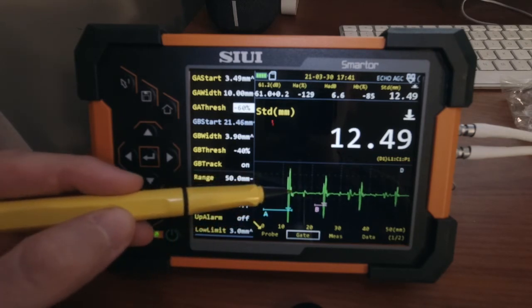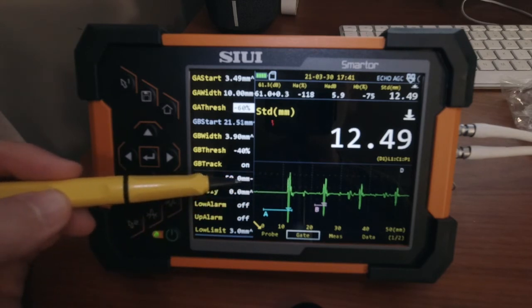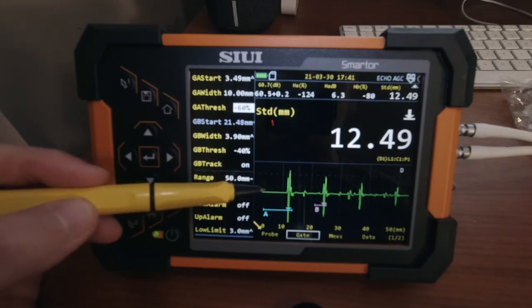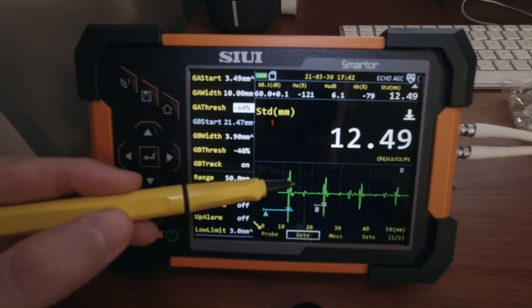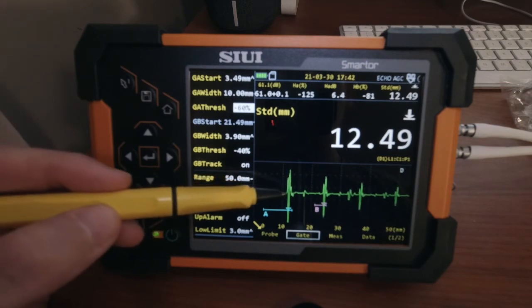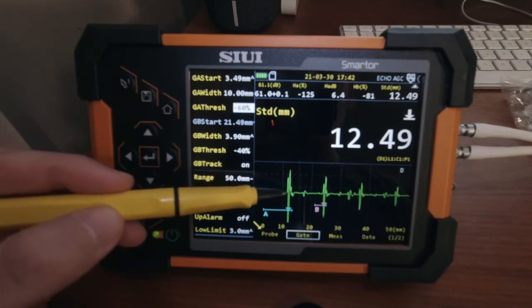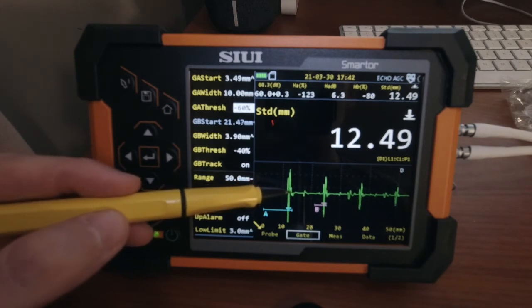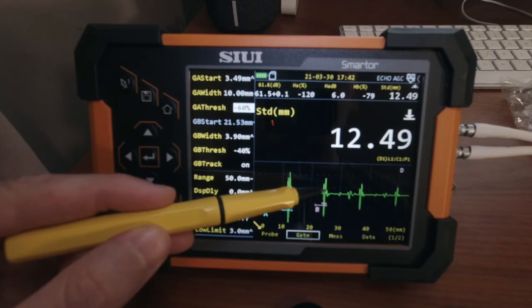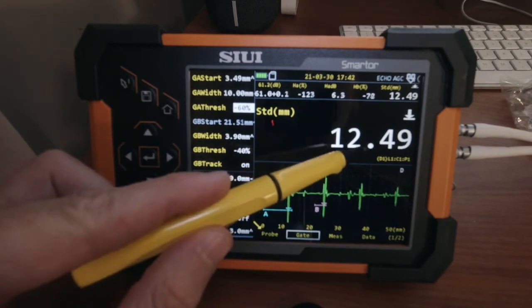Even though the distance between the probe interface and the material, which would include the coating, that may be thicker at the first back wall echo. So it's just being extra cautious, and taking the second back wall echo to calculate its best reading there.